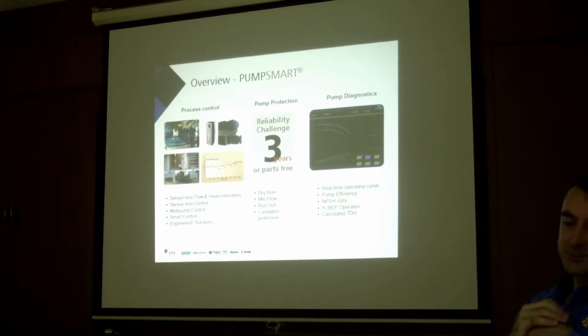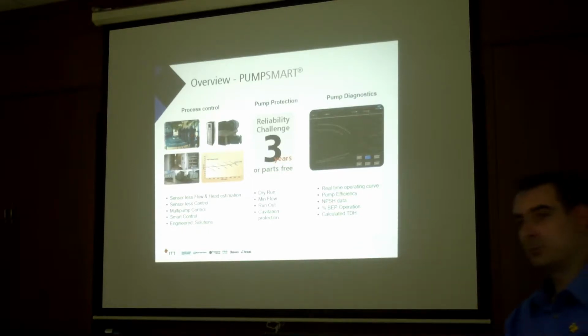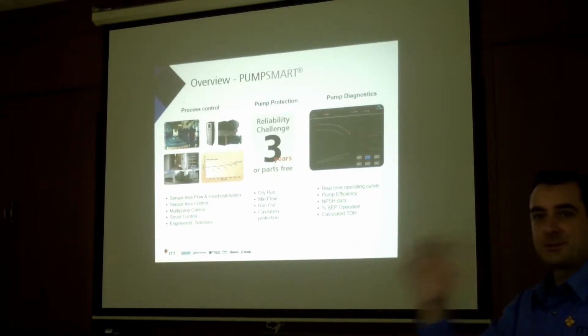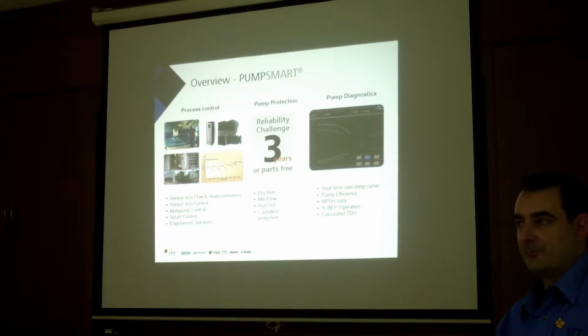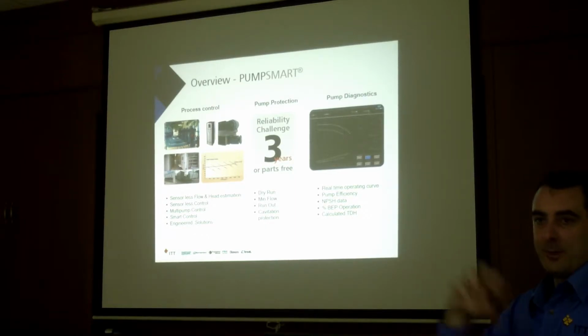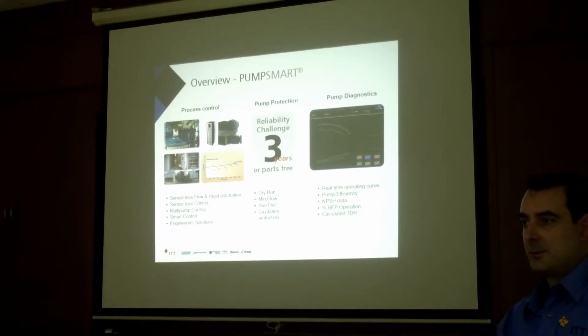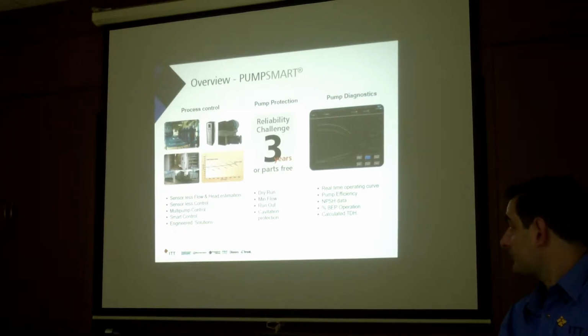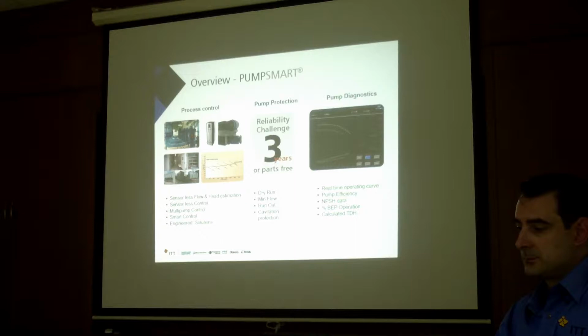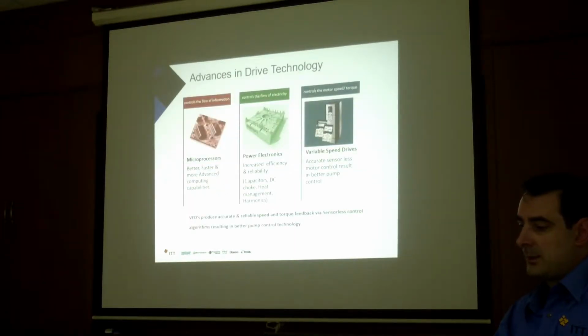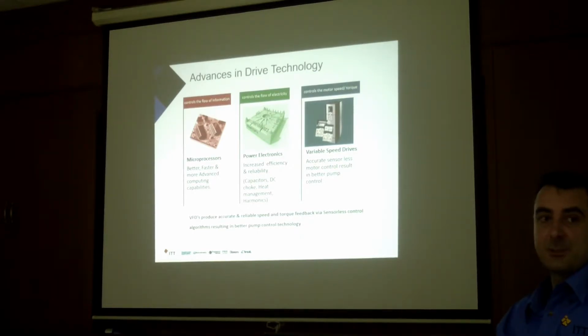Often they'll replace the mechanical seal on one pump and then soon after the other pump will go. It's probably because they overhaul the pump at the same time. So that overhauled pump is now stronger than the old pump. But different system conditions can make a difference too. Compared to even 5 years ago, variable speeds are nowhere near the same as they used to be. They are so much more advanced now.